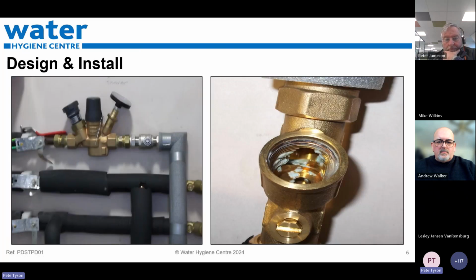Okay, so here we've got balancing valves. Those have got to be set correctly. So 75% of returns are not balanced or circulating. Therefore, we've got areas for Pseudomonas aeruginosa and Legionella positives potential due to that stagnation. And the contractor had to come back to put these right 2 years after the work was completed, and the ward was closed for 2 months. Okay, what was the issue? It was poor configuration, the position of the returns, balancing of the system, strainers and filters.